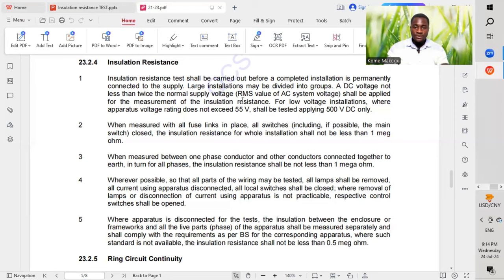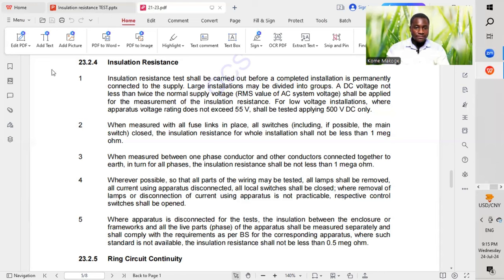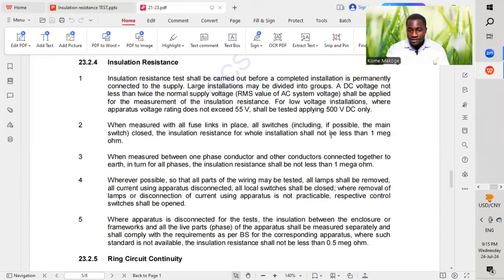The voltage for installations where apparatus voltage rating does not exceed 55V shall be tested by applying 500V DC only. The second point: when measured with all fuse links in place or switches — including, if possible, the main switch closed — the insulation resistance for the whole installation shall not be less than 1 megaohm.